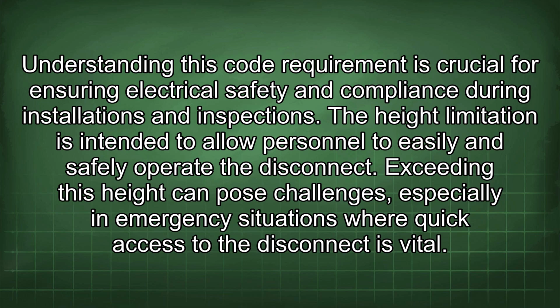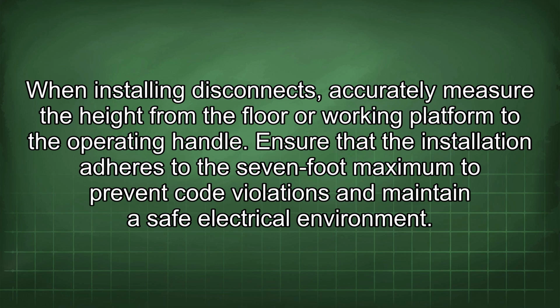The height limitation is intended to allow personnel to easily and safely operate the disconnect. Exceeding this height can pose challenges, especially in emergency situations where quick access to the disconnect is vital. When installing disconnects, accurately measure the height from the floor or working platform to the operating handle. Ensure that the installation adheres to the 7-foot maximum to prevent code violations and maintain a safe electrical environment.